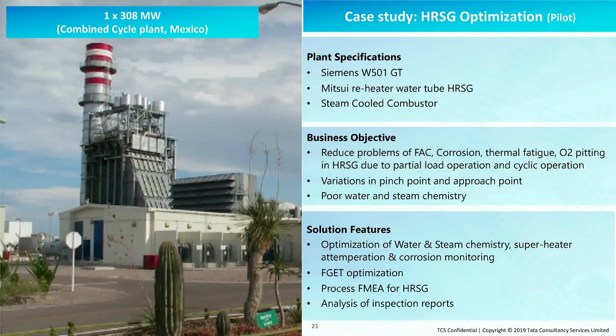In the end, we were able to demonstrate to the customer that optimization of water and steam chemistry, superheater attemperation, and corrosion monitoring was possible, as we successfully replicated past incidents. The process FMEA for the HRSG system was useful in tracing anomalies much faster compared to the existing manual process. Above all, staff didn't have to go through multiple documents while troubleshooting, as the FMEA linked both operations and maintenance aspects of the plant.